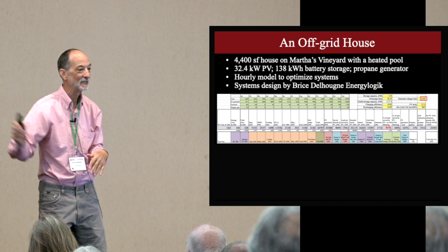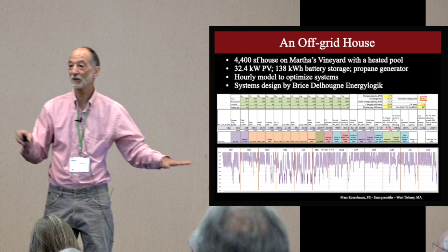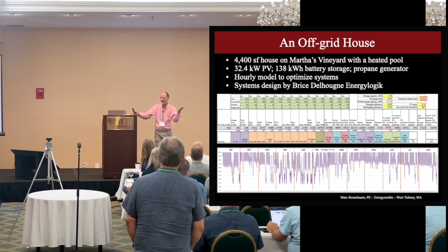So one of my settings here — and by the way, this is the battery, this is how full the battery bank is through the year. It's worse in December and January, but you see some places in summer where it goes down because of the pool. What I learned is that you have to set a generator charge limit on the battery bank. Because when the generator comes on, since you've set a discharge limit, you don't want the battery bank to go below like 15 or 20%. But when it comes on, it doesn't have to fill the battery bank — that's stupid, right? I never thought about it. But now I know I have to put that in as a limit, because that's going to calculate how much propane I'm using. And then I start to play with that — it's like, wow, this is pretty interesting.